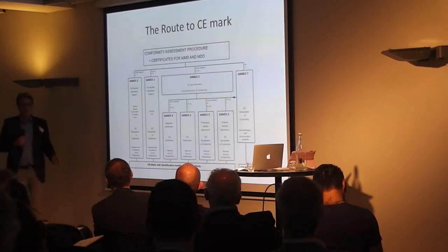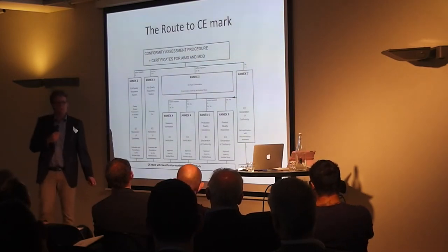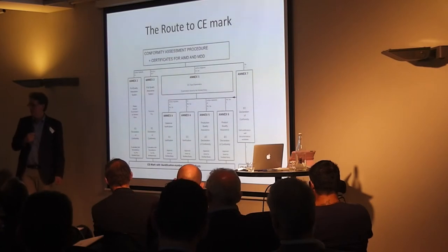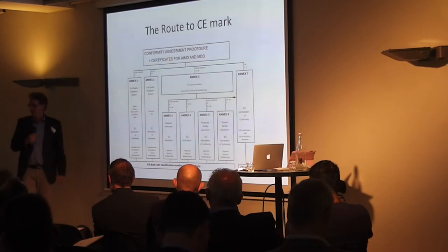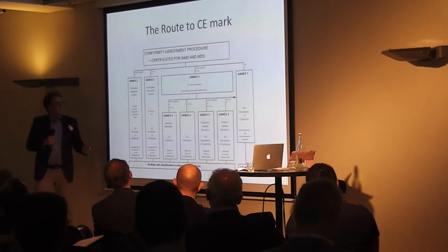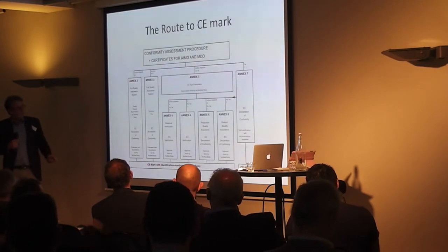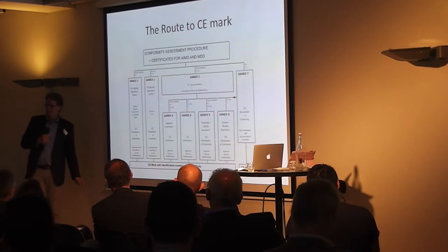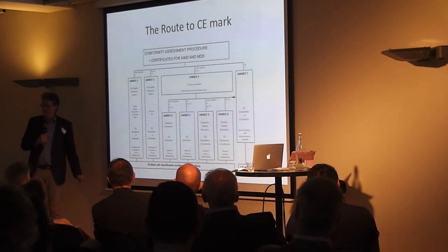I found one notified body in Germany who was willing to type-test the software on a different application. I wondered how they can do that — they can only do that while also looking at your quality system. So these are the different routes, the annex routes of your CE mark, but what also applies is that you always need to meet the essential requirements of the directive.